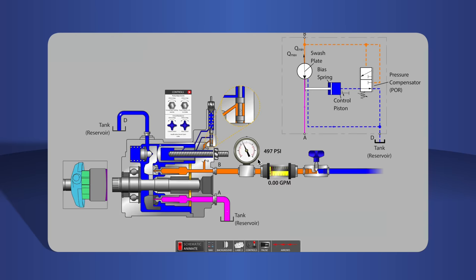The pressure compensator adjustment must be set with the pump running and when there is no system flow occurring.